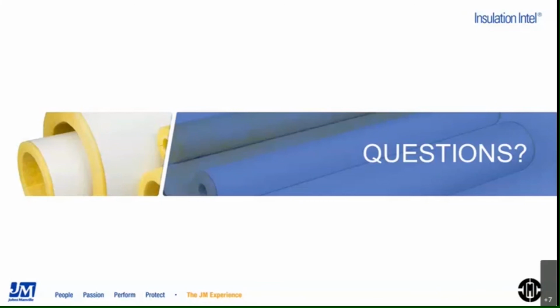It will depend really on a lot of situations, like how thick is the foil. But the whole point of conducting the testing, and that's what we went through, and it was an effort, let me tell you, is because it's a true test where we are evaluating how the flame is interacting with the material and the substrates of the PVC in this case. So again, it will depend on so many things. As long as the foil has been specifically tested and listed and labeled, then sure, it would apply. But just arbitrarily picking up the foil and wrapping it around will not be acceptable because, again, it's listing and labeling.